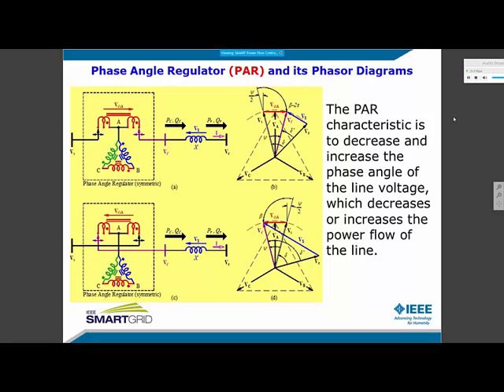Using the transformer and LTC based hardware, a series-connected compensating voltage can reduce the power angle. The same voltage with a reverse polarity can also increase the power angle. As a result, both P and Q flows increase or decrease, as we saw in the last slide.